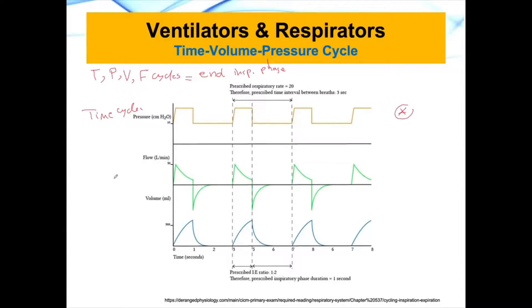If we would like to look at something called pressure cycle — a pressure cycle is different from a time cycle. In a pressure cycle, you are asking the ventilator to increase the pressure to a certain point, and after that point, immediately it stops and allows exhalation. That is called a pressure cycle.